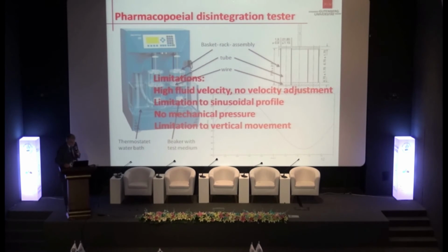Disadvantages is this has quite a high fluid velocity in this instrument. You cannot adjust it. The instrument moves 30 times per minute up and down. It's limited to a sinusoidal profile, no mechanical pressure, and a limitation to vertical movement.